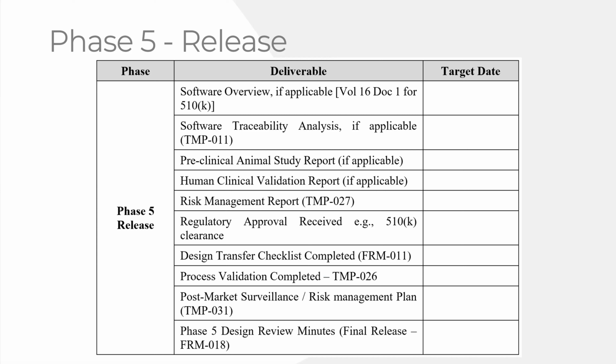So during phase 5, the FDA makes their final decision on your 510K, and you get the 3 letters from the FDA. One is your form letter giving you clearance, one is a copy of your 510K summary, and the last one is your indication for use, form 3881. Those 3 documents are, when you get that email with those 3 documents, now that's your clearance.